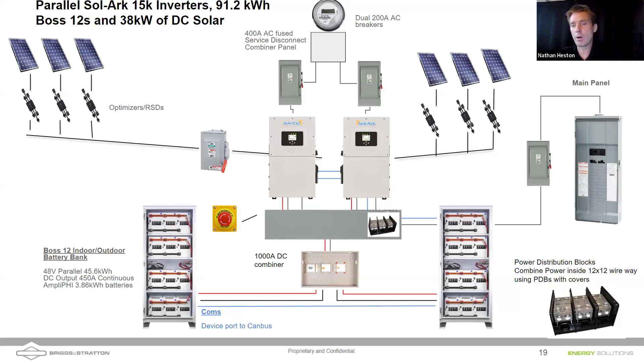The last thing I want to point out on screen, we're still showing the optimizers and rapid shutdown devices. When taking the power output of dual Sol-Arks in parallel like this, you want to combine them before sending that out to the load center. So I'm showing the use of a power distribution block to combine the AC outputs of these inverters before they go into the main loads panel. You can use those for battery combining as well. These come in all sorts of configurations, with 4-aught out, 1-aught in, or number 1 wire in, etc.